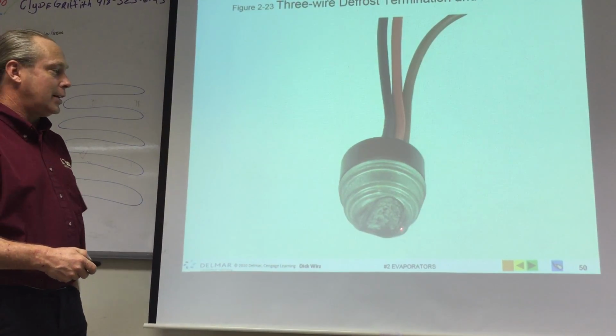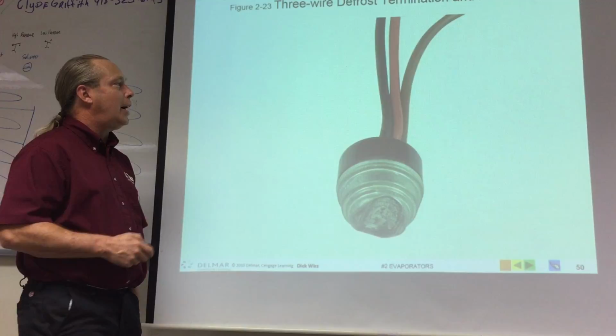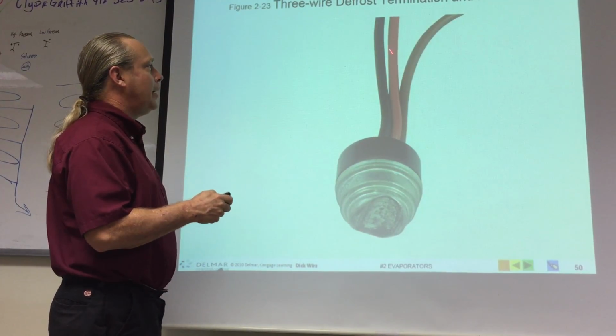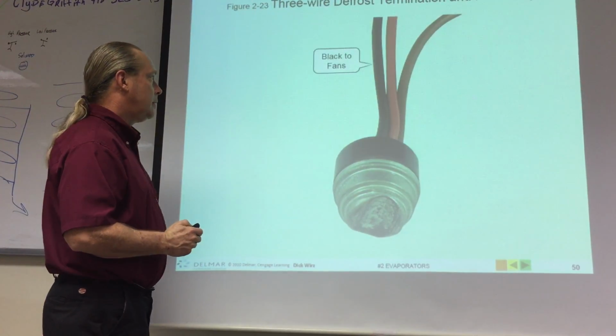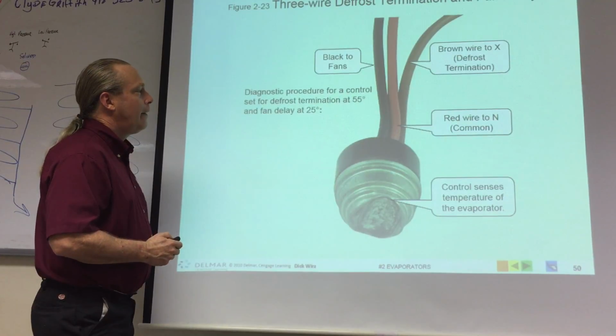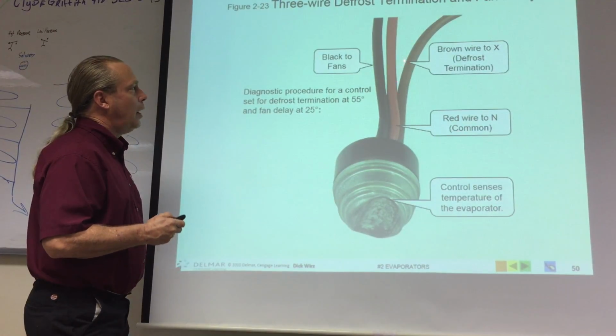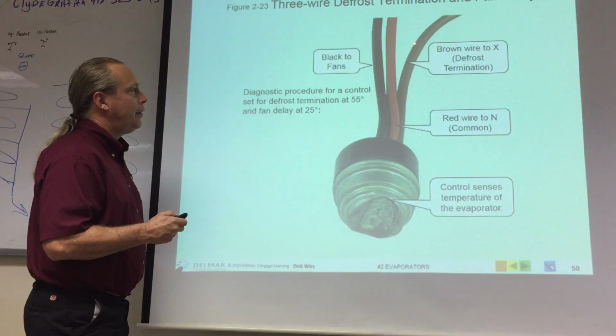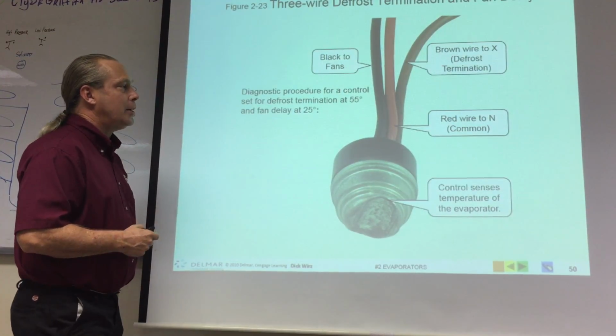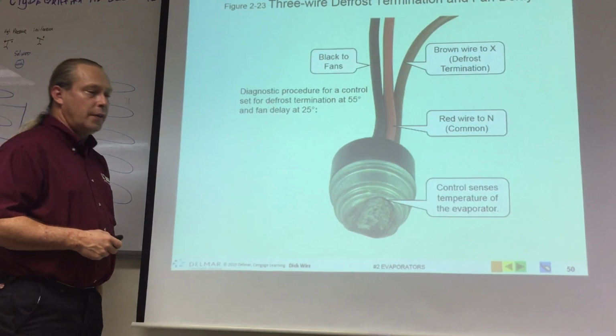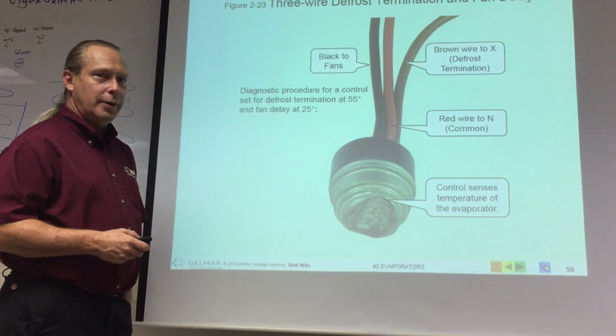And there's what it looks like. It's got a little curve to be mounted on a pipe. You can see the black, the red, and the brown wire. So here's our red wire to neutral, the black wire from the fans, and the brown wire to the X terminal on the defrost motor.